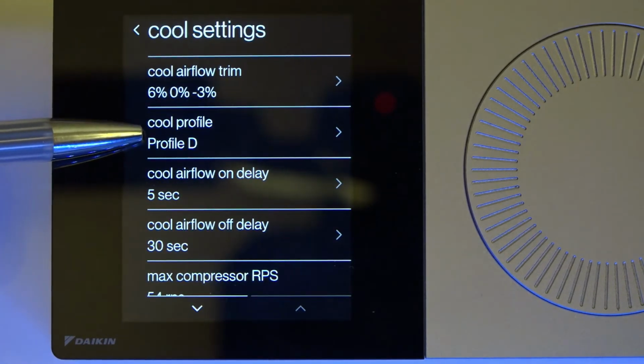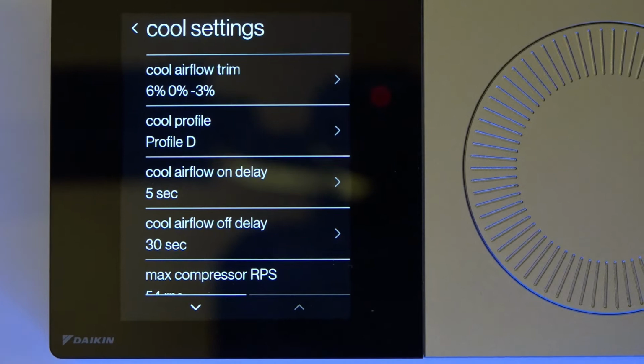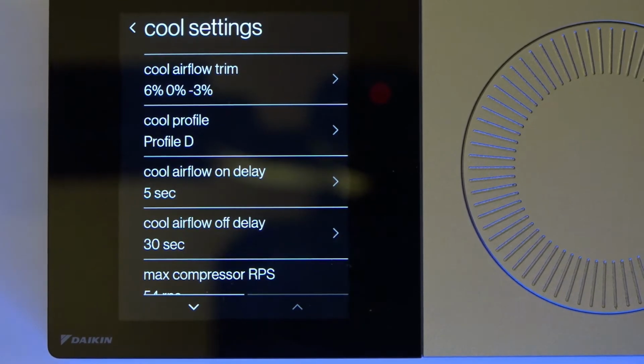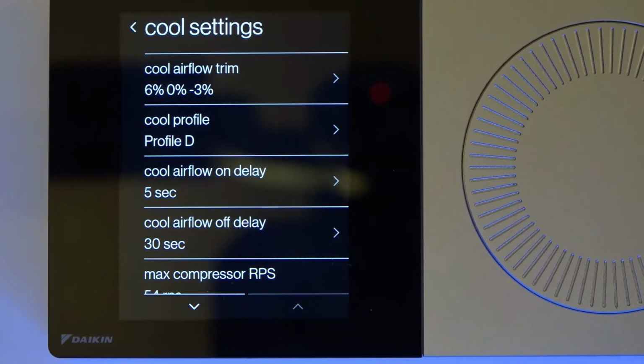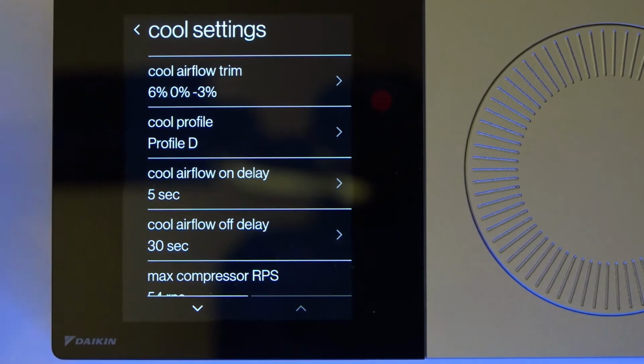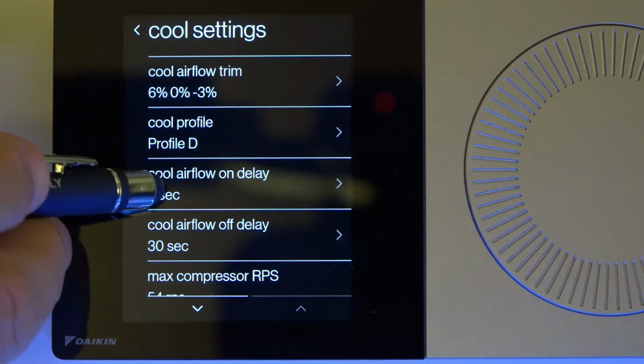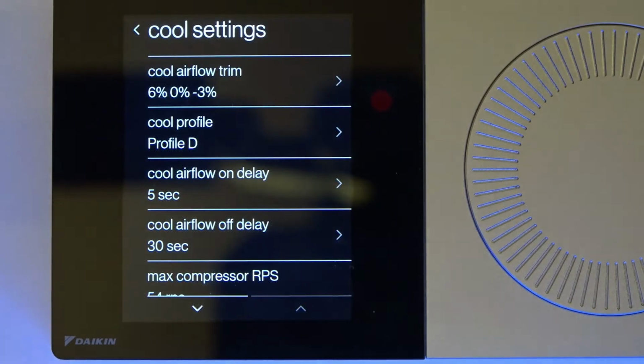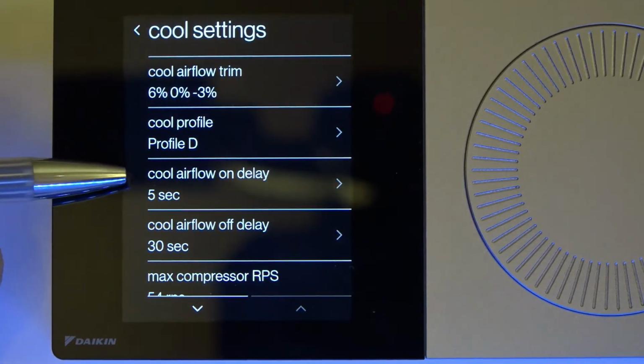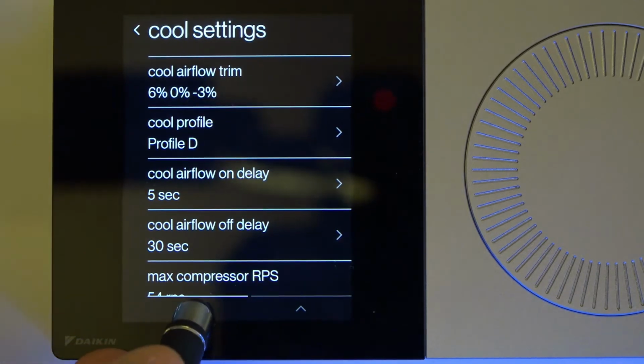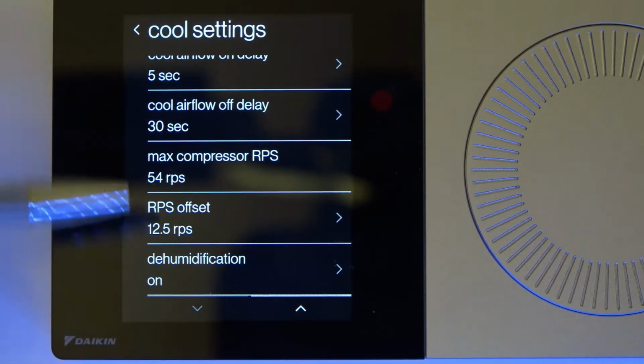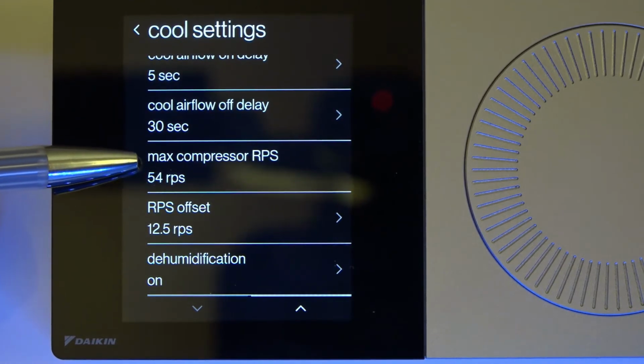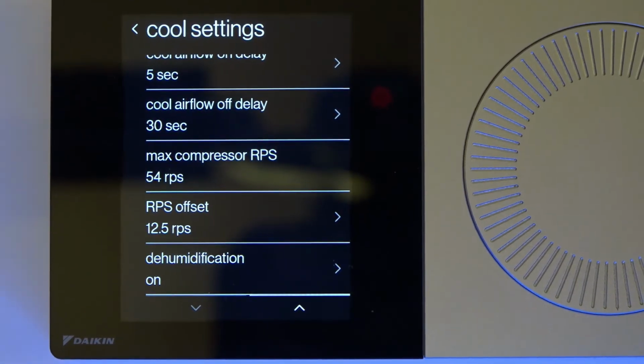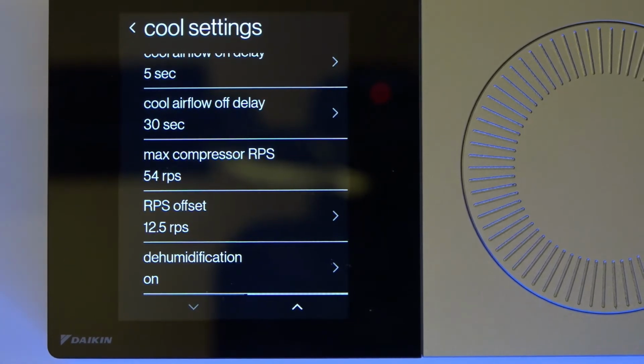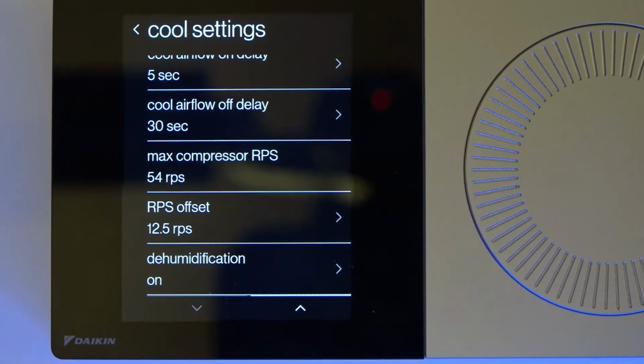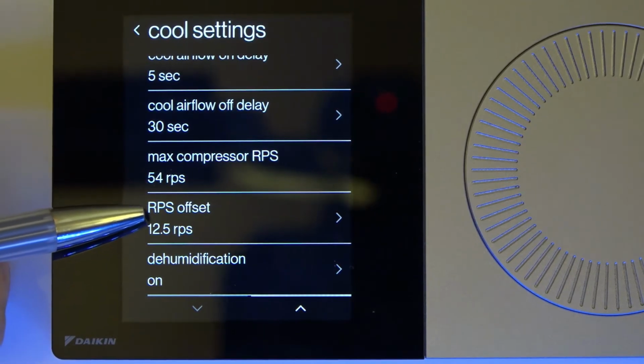we default the cooling profile D. That is the algorithm on how the blower ramps up and down. D is its default, and I recommend leaving it there. And I can change my delay on. I accidentally hit the screen. My delay on and my delay off in this section. I can also look here, max compressor revolutions per second. In this particular model, it's 54 revolutions per second. And then you can tweak it just a little bit.